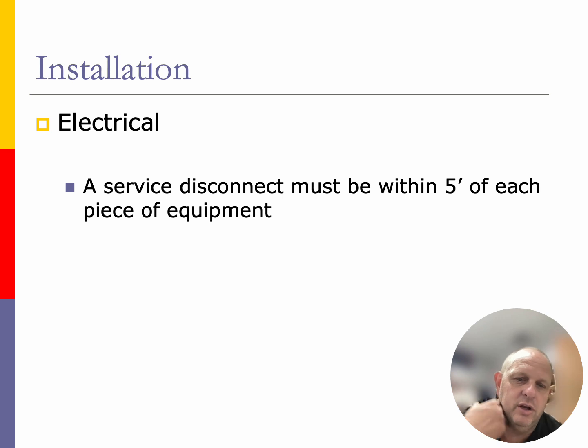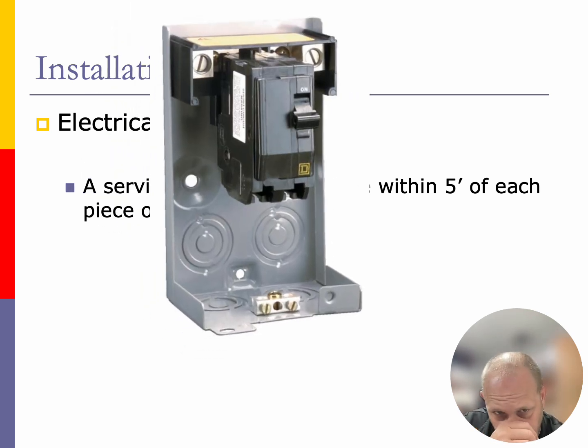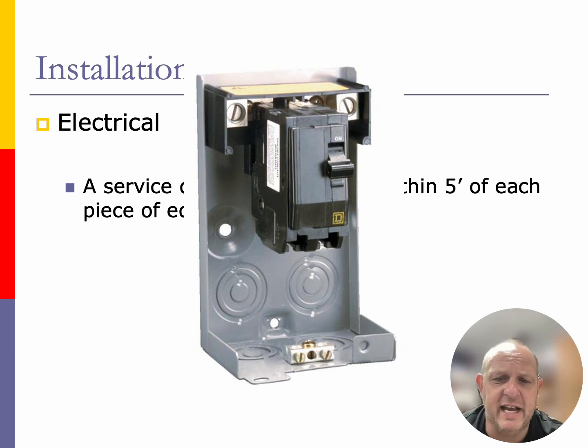This is an example of a disconnect switch that we would be installing. We would bring the power supplies into the sides up in here. This breaker, like a breaker that you have seen in electrical class, hooks on with feet on the back side here, and it's going to bring that power down into two screws that are located on the load side of that switch itself. And then we'll use some liquid tight connectors to come out, and we'll go to our outdoor unit and power the outdoor unit in that way.